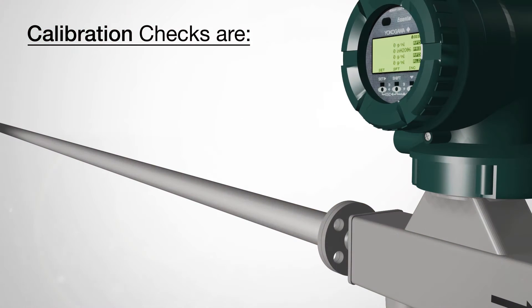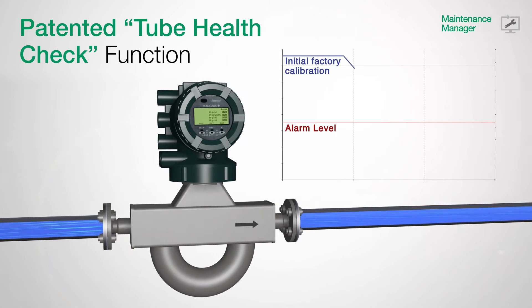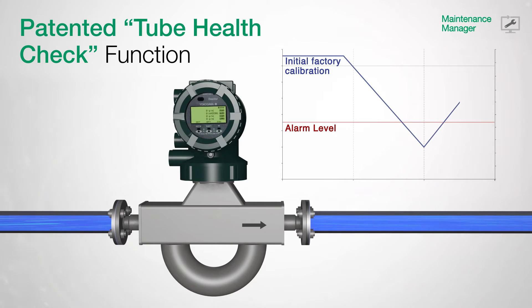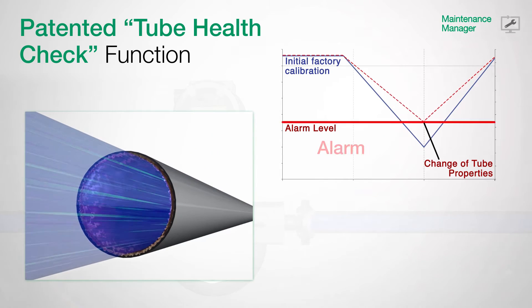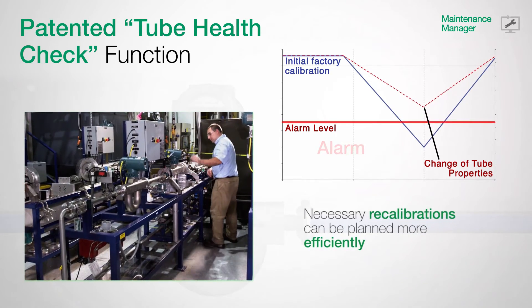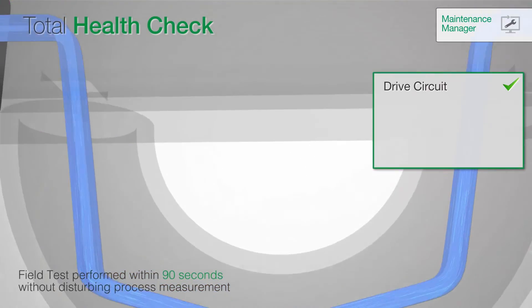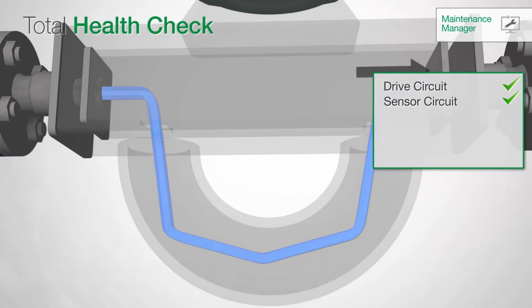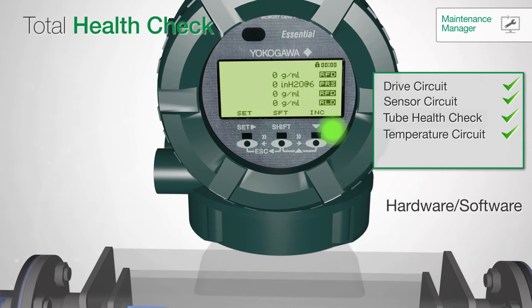In regards to maintenance, calibration checks are costly, time-consuming, and cause downtime in production. But with the newly developed and patented total health check, a calibration check of an installed Rotamass can be performed while in operation without disturbing running measurements. Influences on the meter are diagnosed at an early stage, thus eliminating downtime and reducing your costs. Any necessary recalibrations can then be planned more efficiently. Tube health, as part of the total health check function, completes the meter verification. Yokogawa's FieldMate delivers a complete report about the actual health status and indicates a clear verification result within 90 seconds.